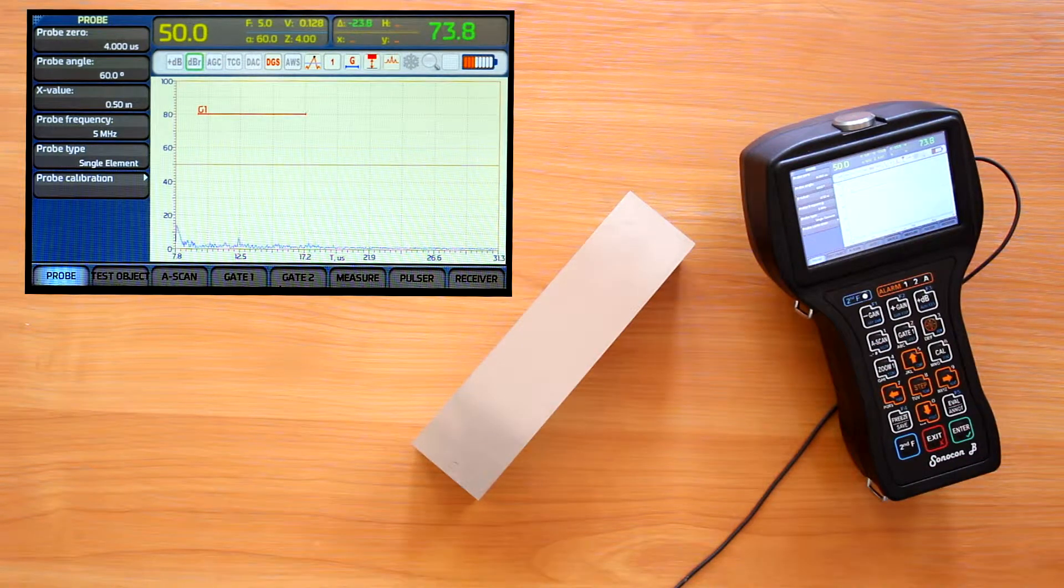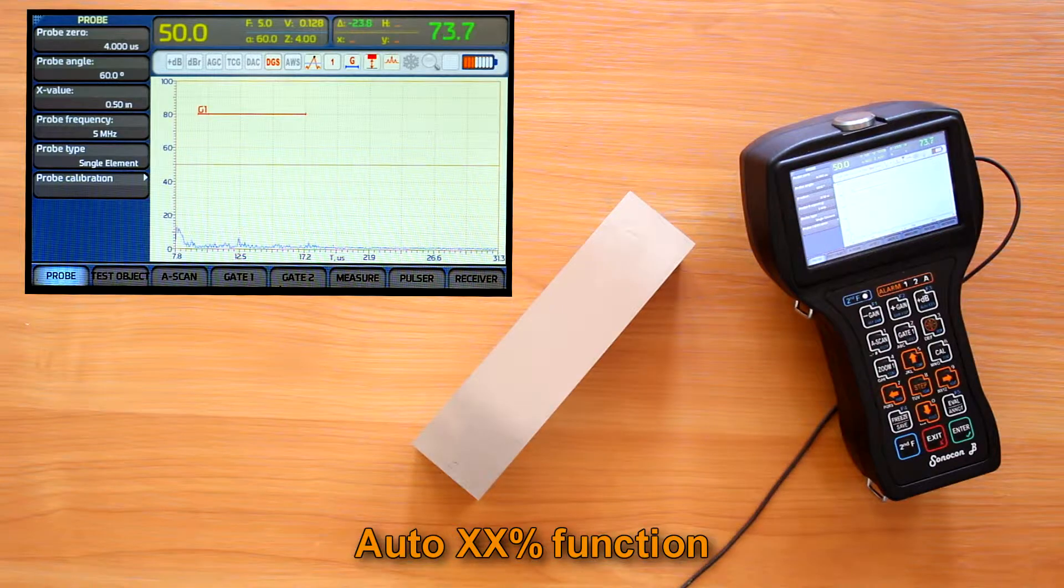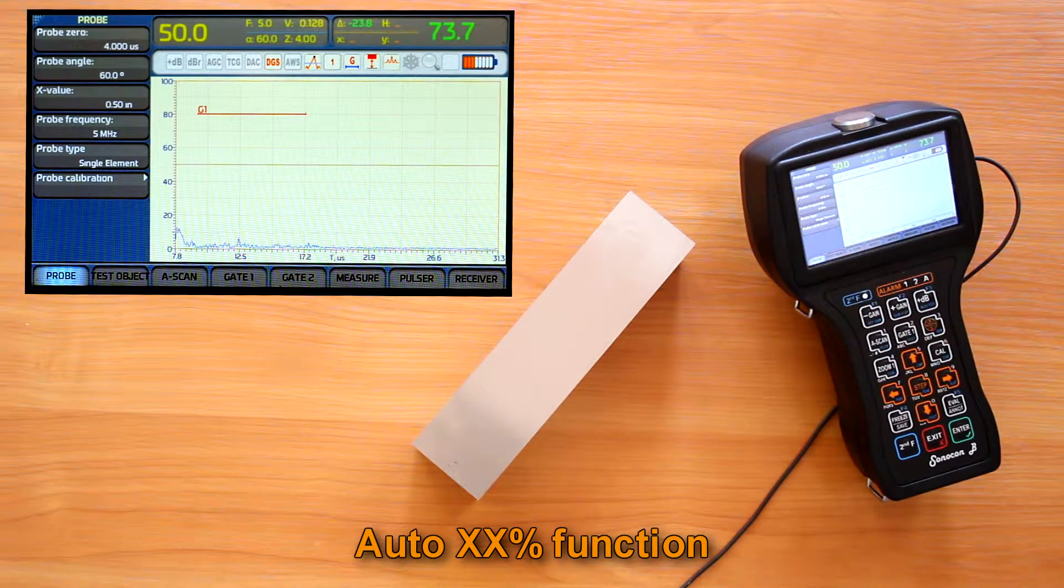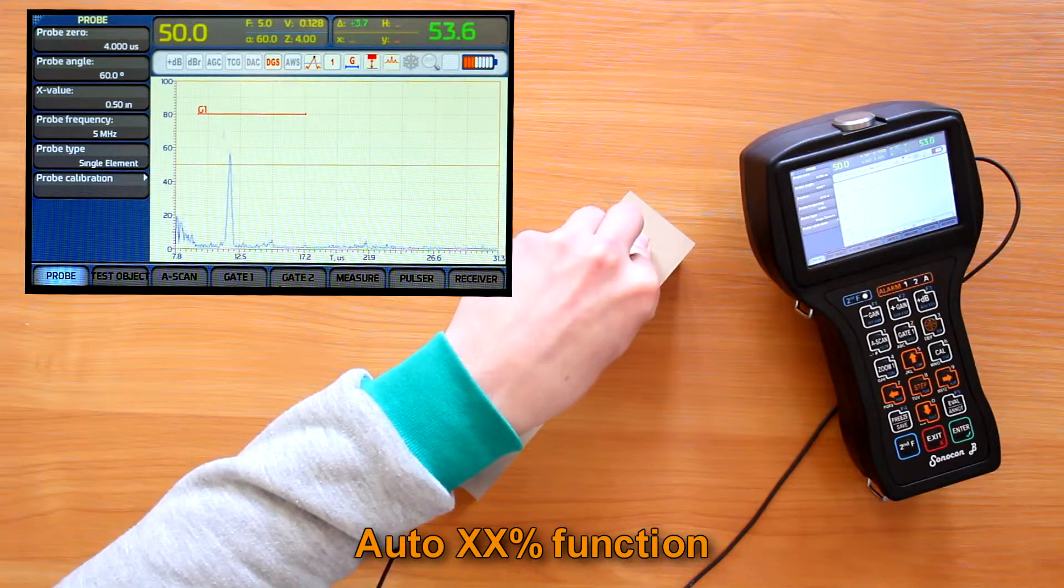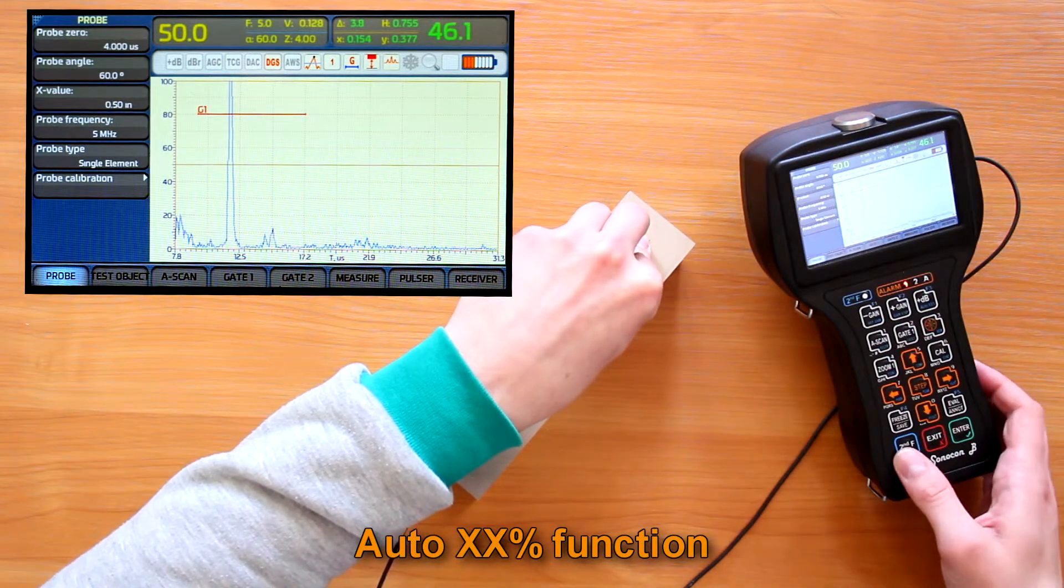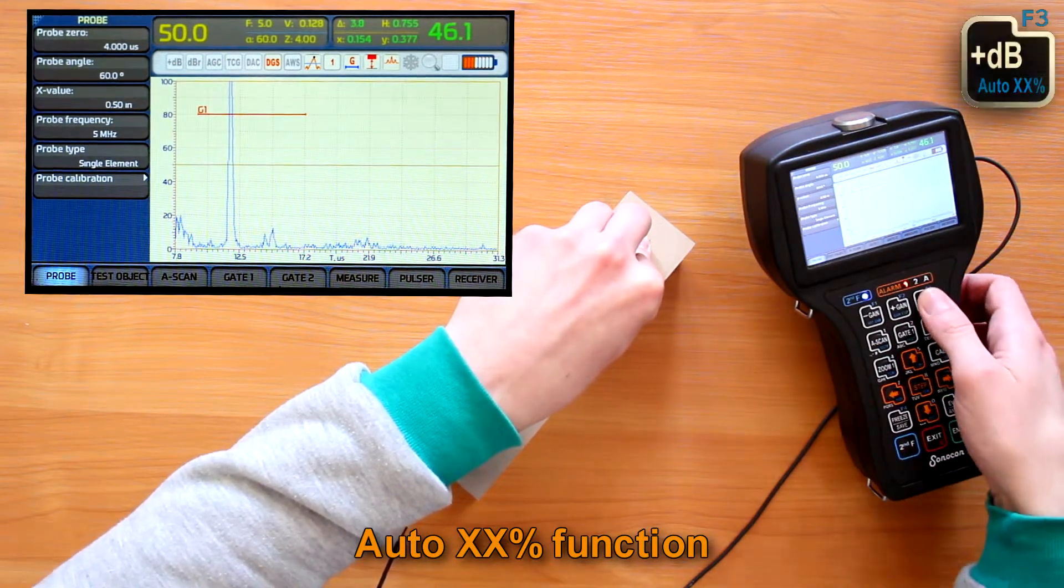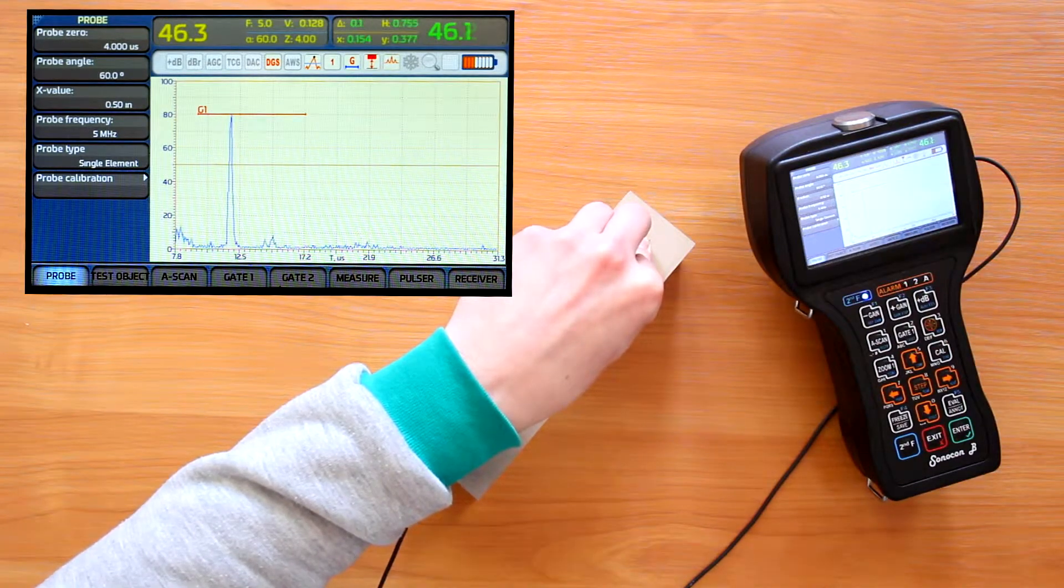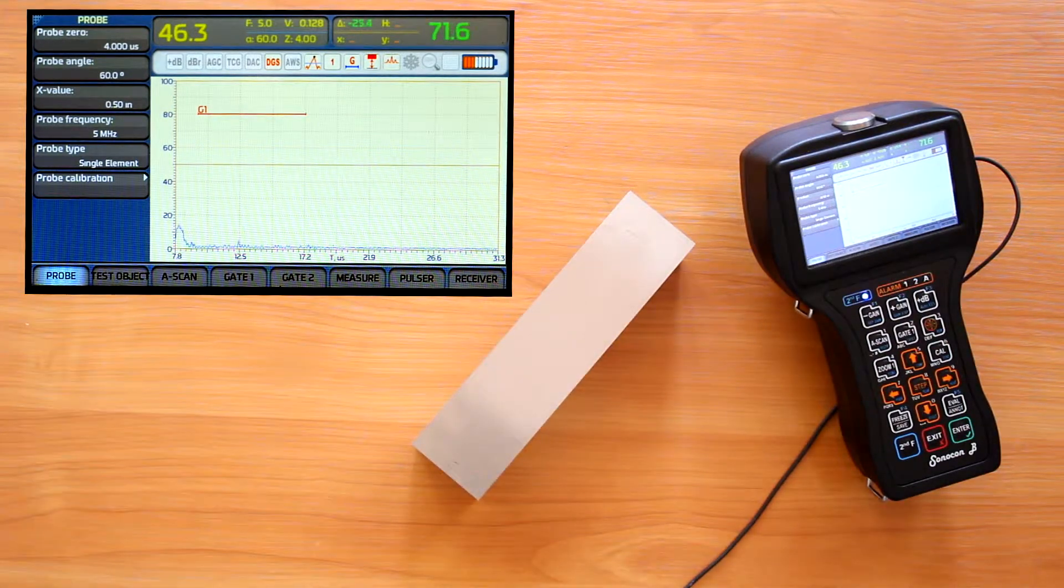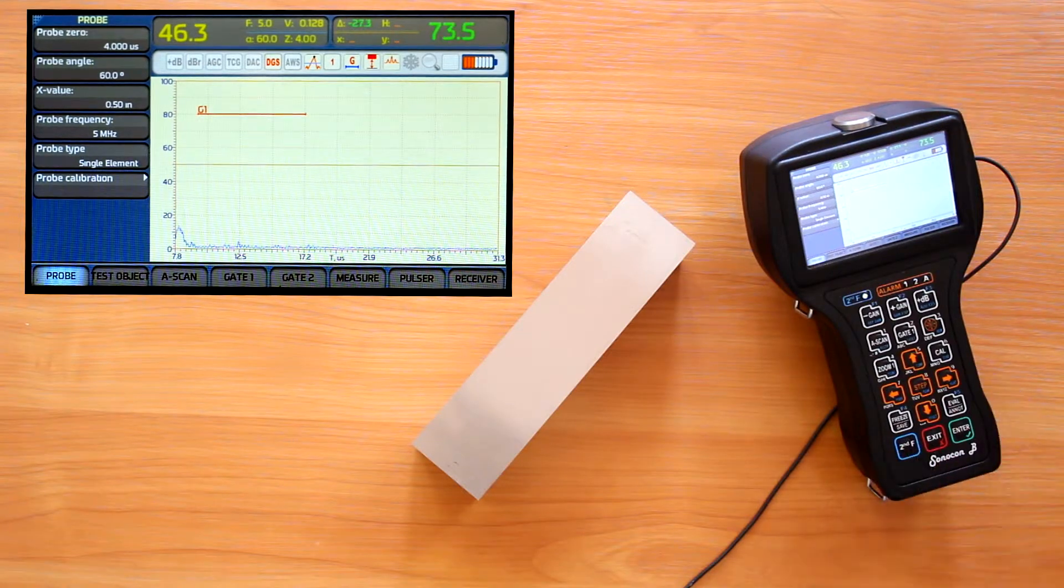Next function, AutoXX% can be used both during setup and indications evaluation. It automatically adjusts the gain to put the maximum signal amplitude in the gate to the reference level, that is to 80 or 50% vertical scale depending on the original standards.